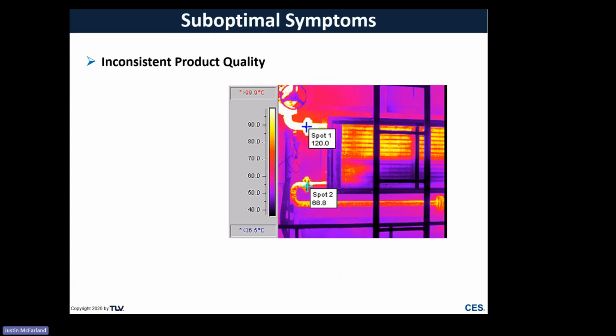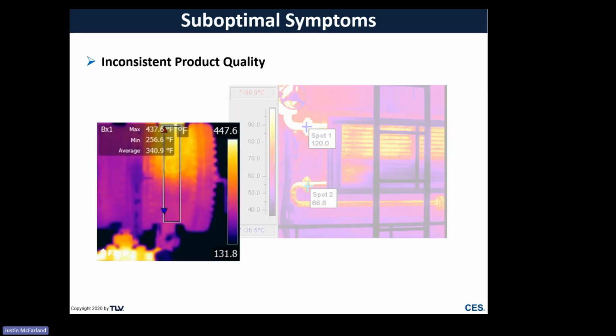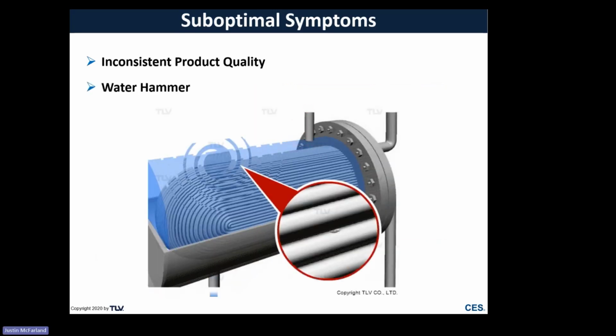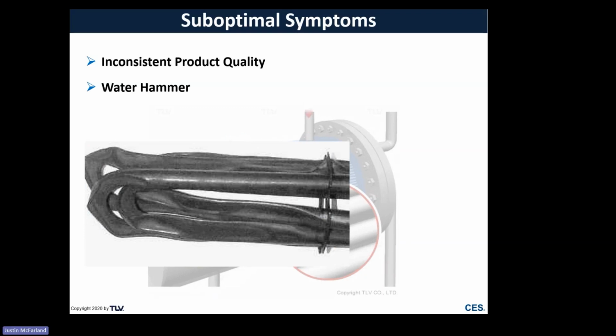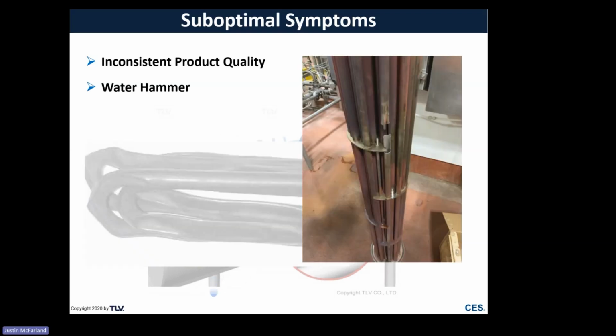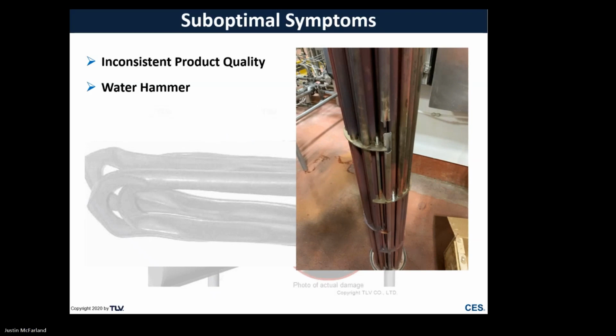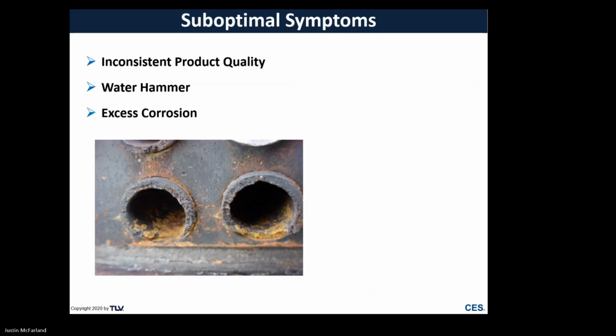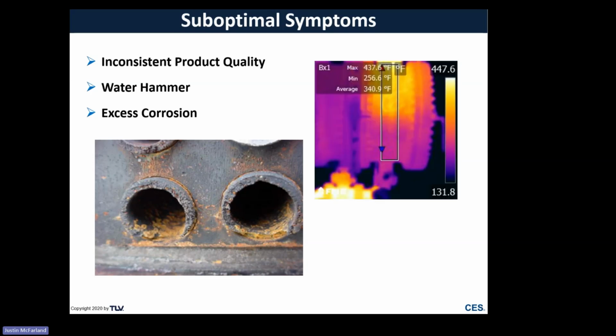So we saw this image. Things like flooding are going to produce inconsistent product quality just because we're going to have temperature control issues. Oftentimes that'll result in water hammer, just due to the presence of hot vapor near a flooded coil, or cold condensate that's backed up. You can get tubes that become broken, ruptured tubes like you see here. Condensate inside the tubes, especially if it's held there for a long period of time and allowed to subcool, can cause excess corrosion. So that's going to degrade your U value as well.